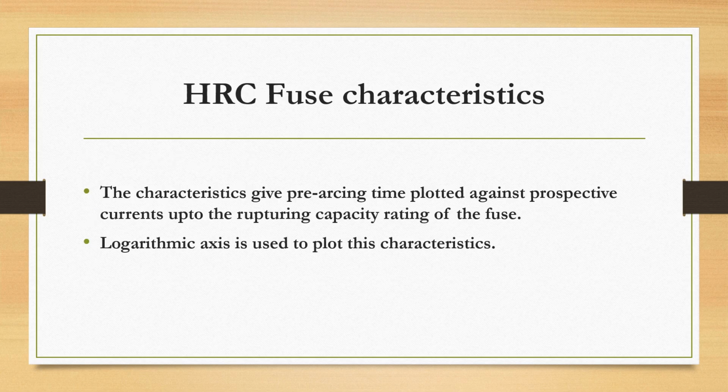While selecting HRC fuse in different applications, its characteristic plays an important role. Normally, the characteristic gives pre-arcing time plotted against prospective current up to the rupturing capacity rating of the fuse. This characteristic is plotted generally on logarithmic paper.